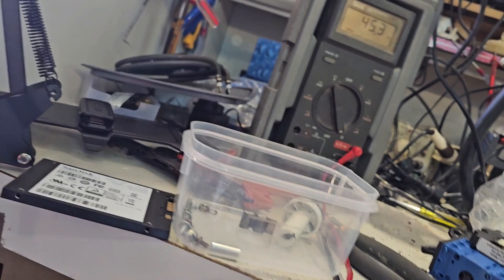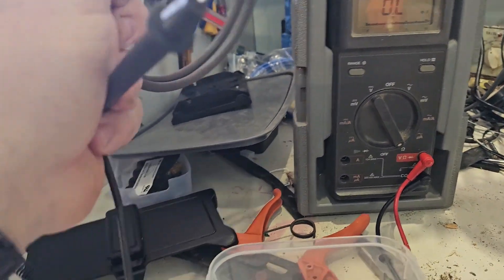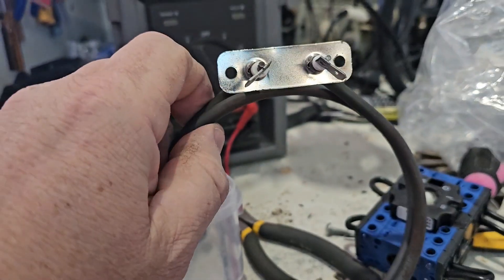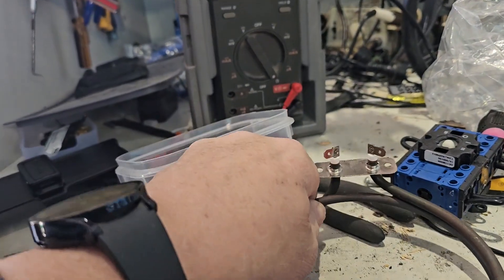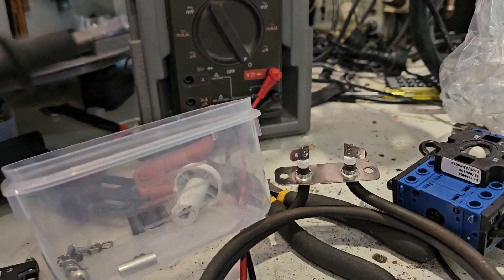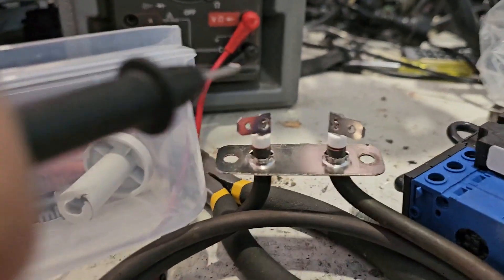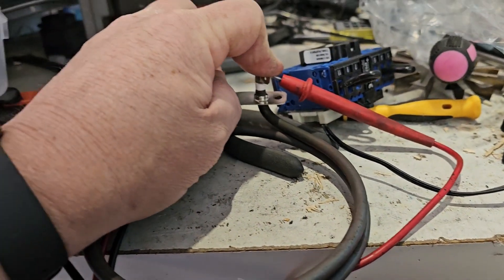Now on the old one which is over here, it's busted. The way you work it out is just Ohm's law, checking what the resistance is. 240 volts divided by what wattage your oven is. We'll put that across there. 32 ohms, way too low. It's almost like a short to it.